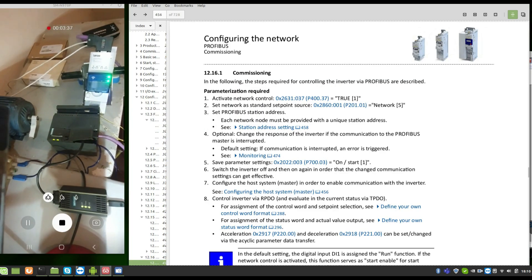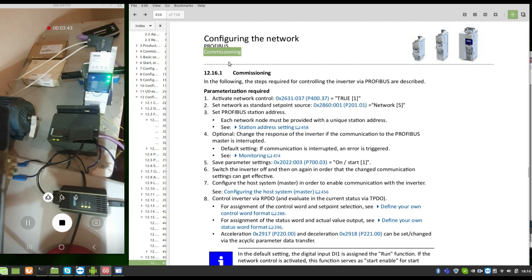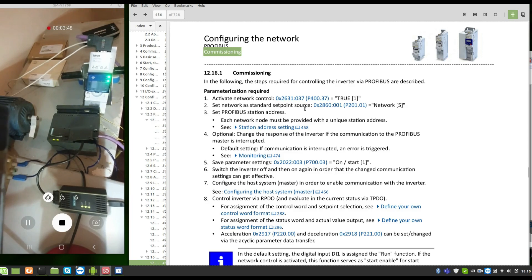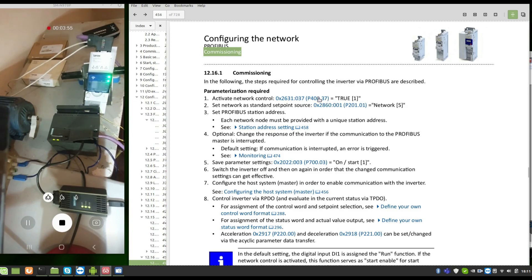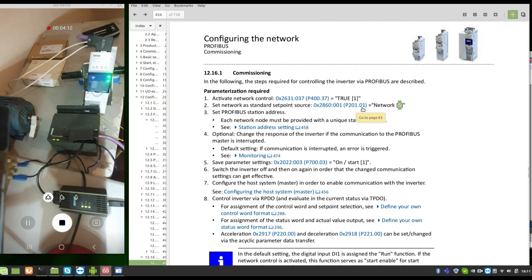Here's the configuration network. We have a Profibus commissioning. To activate the control we have to go to parameter P400.37. This is the index and sub-index. You must put true because this is the network control and set the network standard setpoints. We must put five here in the P201.01.